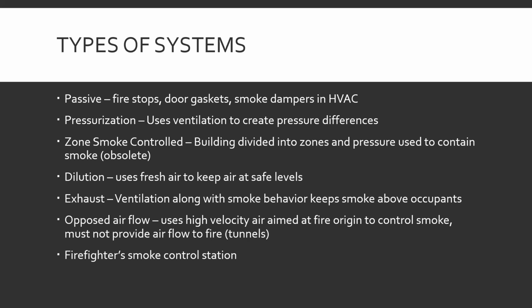Pressurization. Already talked about it. Ventilation that can create pressure differences. That's that whole smoke can't go from low pressure to high pressure that we talked about. Zone smoke control. The building is divided into zones and pressure used to contain smoke. Obsolete. Like it says, this is going away. This is kind of like pressurization, but more generalized. For example, if you have a 4-story building, the first floor will be pressurized separate from the second floor, which is separate than the third floor, which is separate than the fourth floor. You get the picture. Or the east wing of the building is pressurized different than the west wing of the building. So it's more of a general, keeping individual floors or large areas pressurized from one to the other.